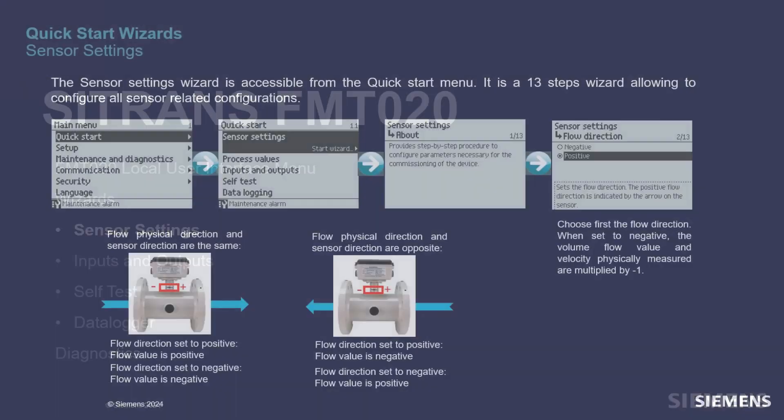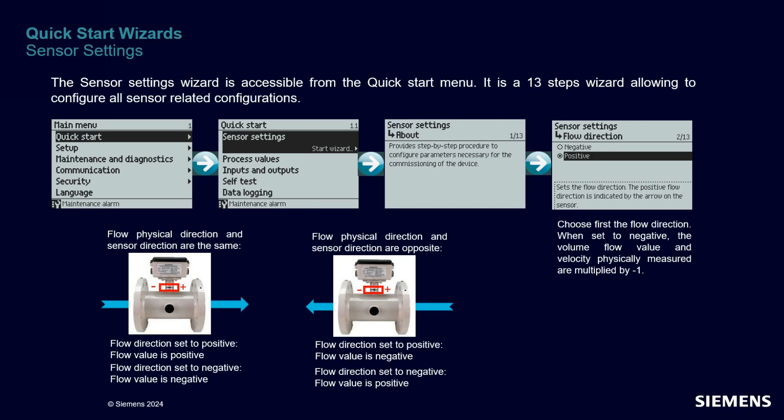Let's start with the wizards of the sensor settings. The FMT-020 has numerous parameters for all of its features, and the team designed many wizards to make commissioning simple and easy. This sensor settings wizard is composed of 13 steps covering all aspects of the sensor parameters. It starts with defining the flow direction for which the product will report positive flow values.